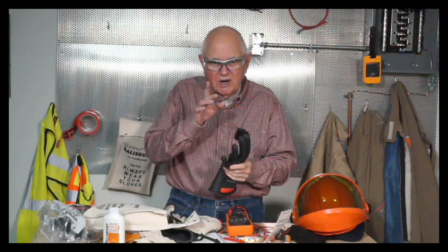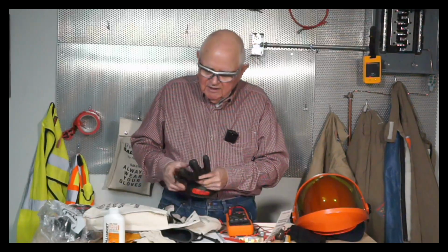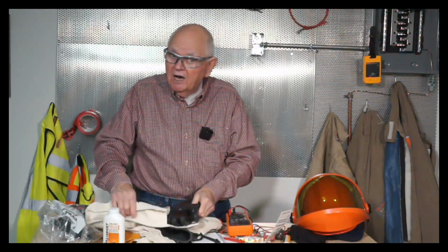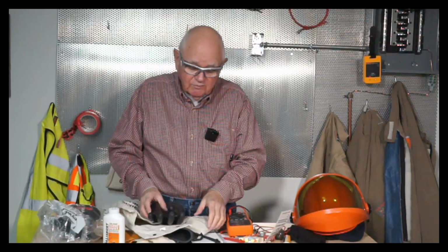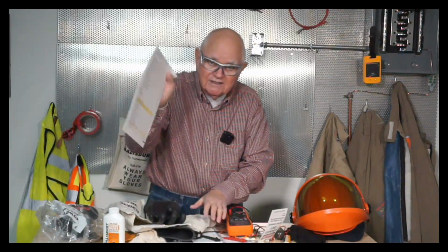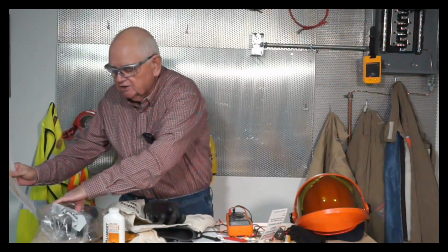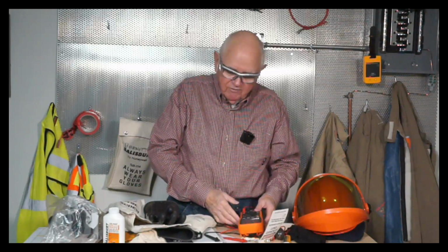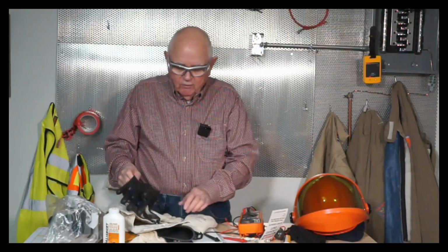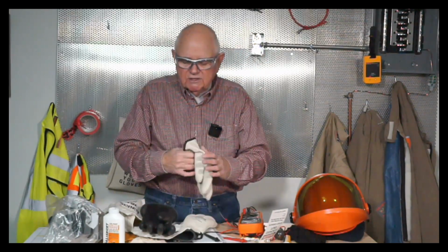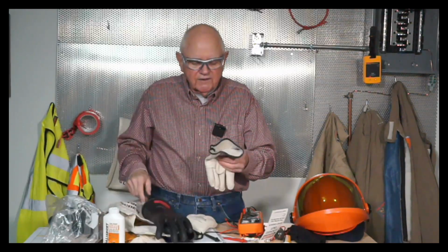Make sure you do a proper and good air test on your gloves. It should all be covered in your written electrical safety procedures, something like this or whatever you have, that tells you how to check those gloves out. It's part of your glove safety program, whatever you may have in place. Okay? So we also check the protectors. We make sure that it's the proper size protector for the glove.